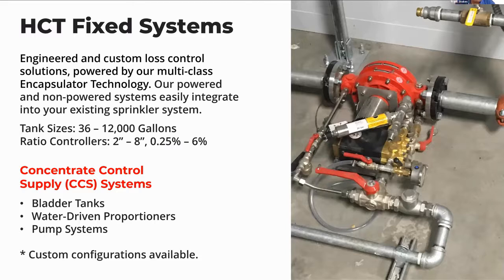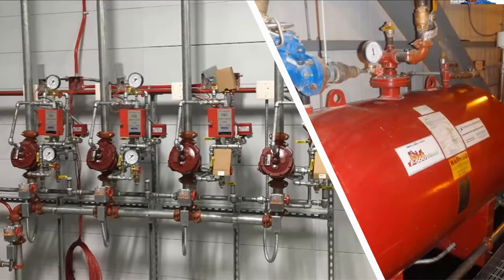We have powered and non-powered systems to integrate into existing sprinkler systems, with tank sizes ranging from 36 gallons to 12,000 gallons, and ratio controllers from about 0.25% up to 3%. Our concentrate control supply systems include bladder tanks, water-driven proportioners, pump systems, and custom configurations as needed. This photo shows sprinkler risers, and to the right is a bladder tank that supports these risers with the F500 product.